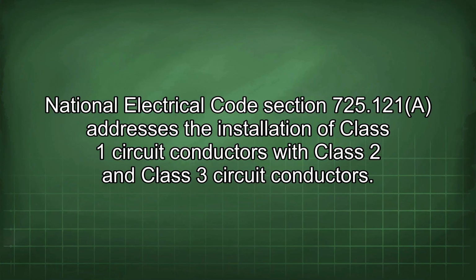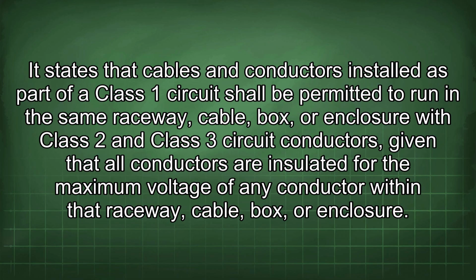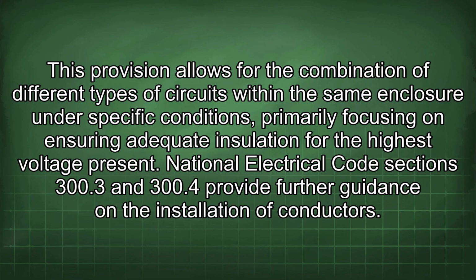National Electrical Code Section 725.121 addresses the installation of Class 1 circuit conductors with Class 2 and Class 3 circuit conductors. It states that cables and conductors installed as part of a Class 1 circuit shall be permitted to run in the same raceway, cable, box, or enclosure with Class 2 and Class 3 circuit conductors, given that all conductors are insulated for the maximum voltage of any conductor within that raceway, cable, box, or enclosure. This provision allows for the combination of different types of circuits within the same enclosure under specific conditions, primarily focusing on ensuring adequate insulation for the highest voltage present.